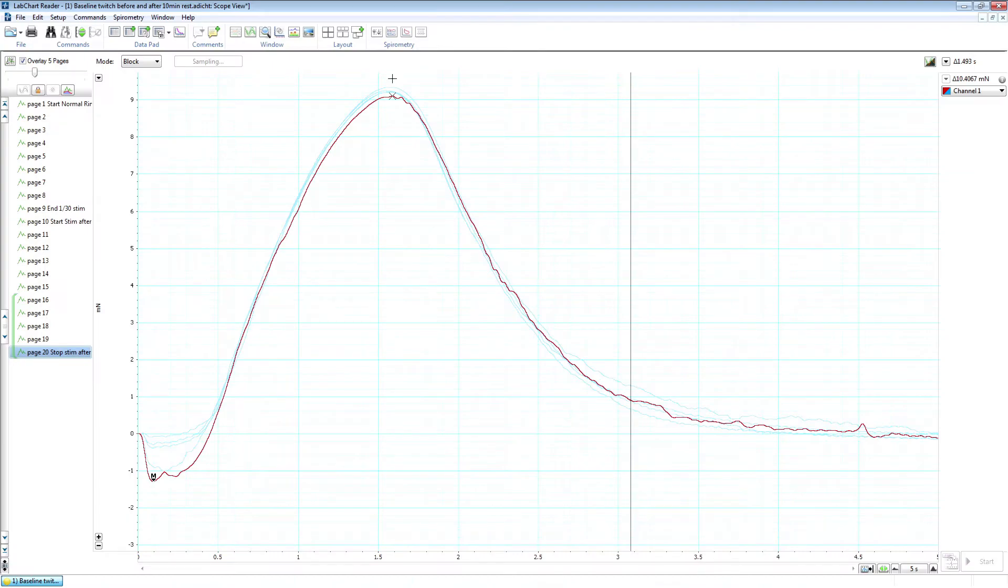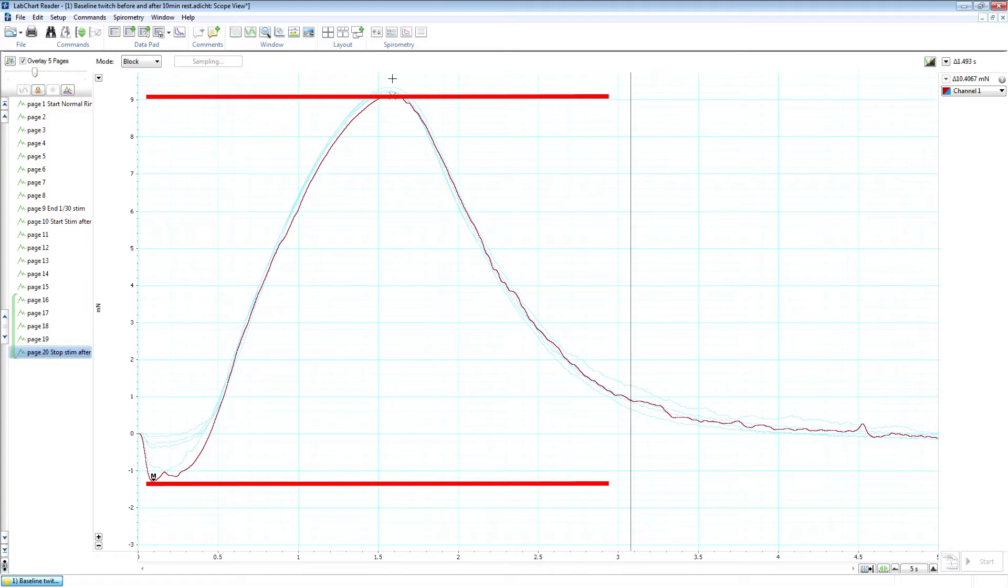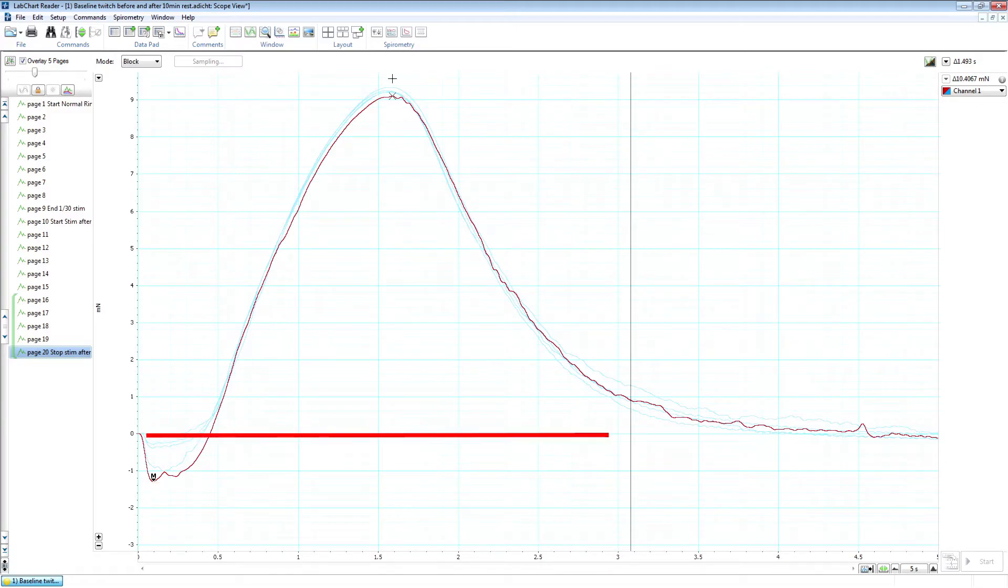You can see force, which is the Y axis reading on the bottom of these two numbers up here. But the X axis reading time is also shown, and that's shown just above that number here. And so when you use the marker, you're measuring from the marker to the cursor. If you don't use the marker, then you'll be measuring from zero to the cursor, and that's not necessarily what you're trying to measure.